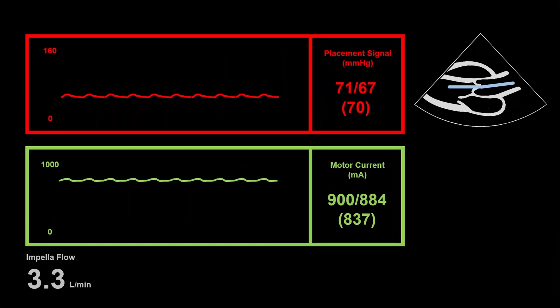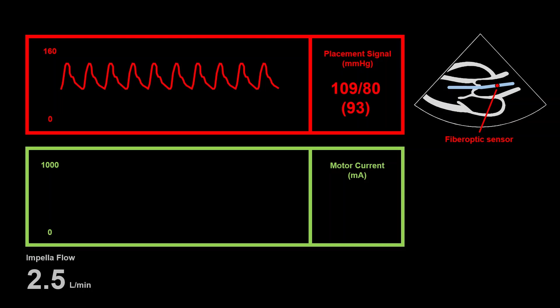Next, we must consider if the Impella is in the correct position to deliver the reported cardiac output. Here we see relatively flat waveforms in the green motor current tracing and the red placement signal tracing. The red placement signal tracing reflects true arterial pressure detected by a fiber optic sensor in the Impella catheter. The green motor current tracing reflects the amount of energy and flow through the cannula.